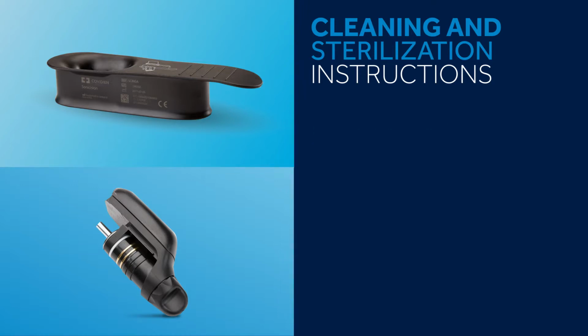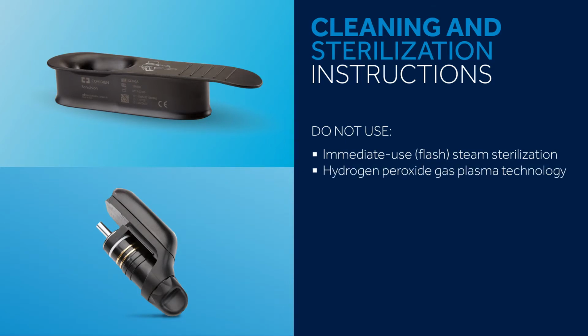Use only the sterilization method that is recommended and qualified as described in these instructions. Do not use immediate use or flash steam sterilization, hydrogen peroxide gas plasma technology such as STERRAD systems, ethylene oxide or EO, or gamma sterilization to sterilize any component of the Sonicision system. Exposure to these alternate forms of sterilization will damage the equipment and compromise sterility.